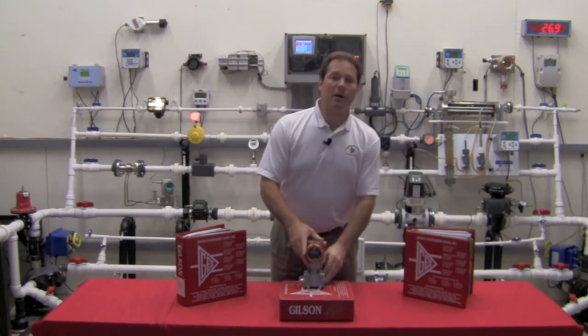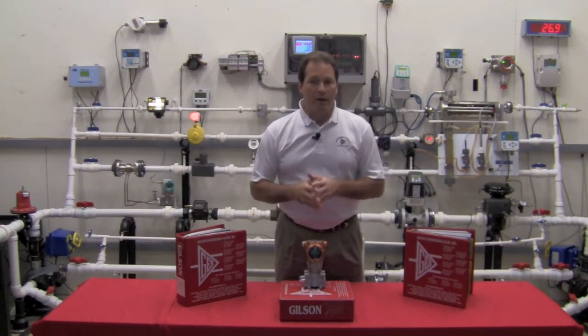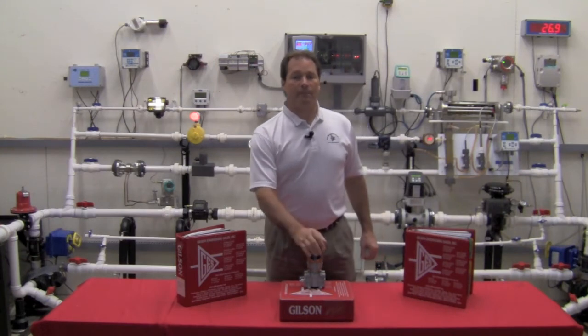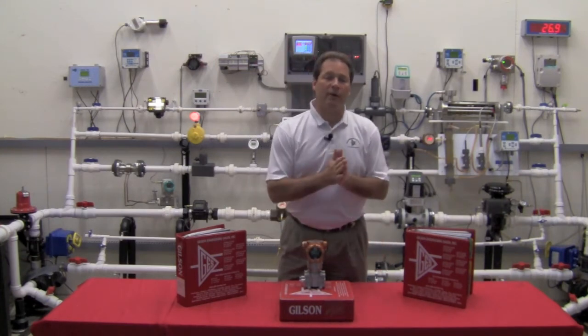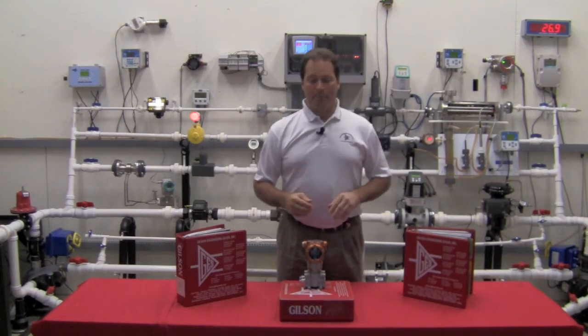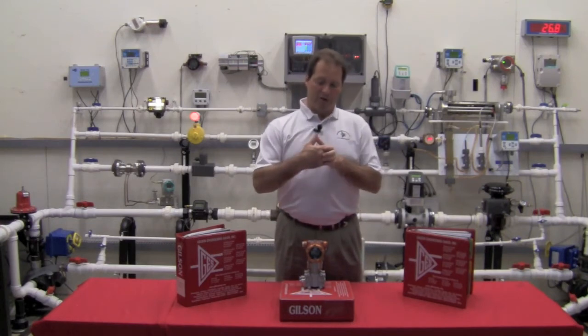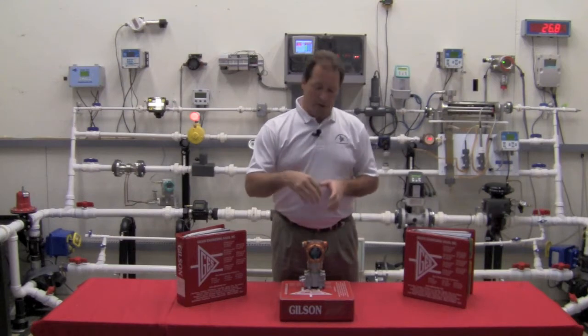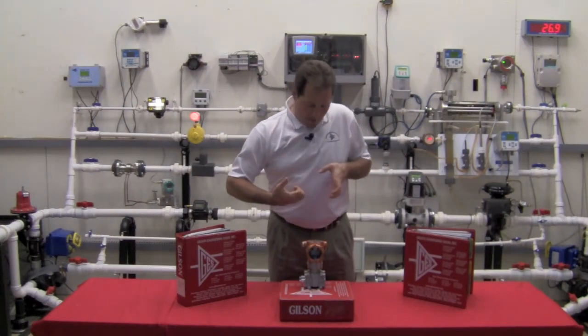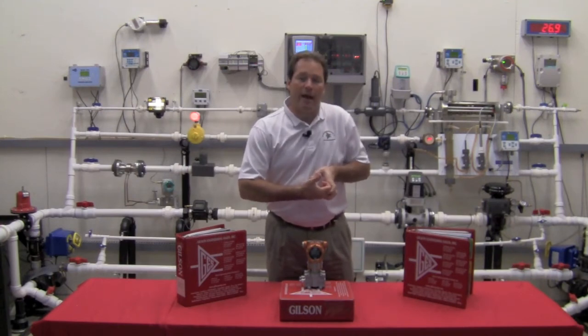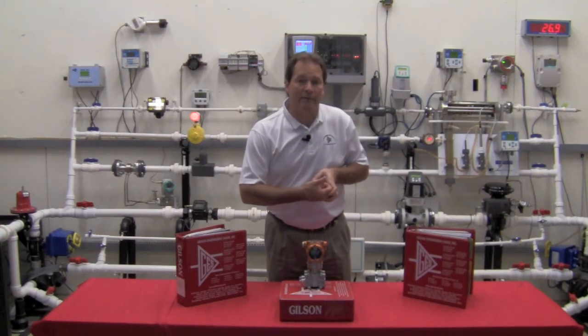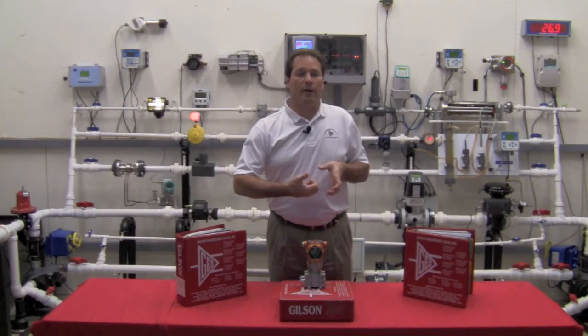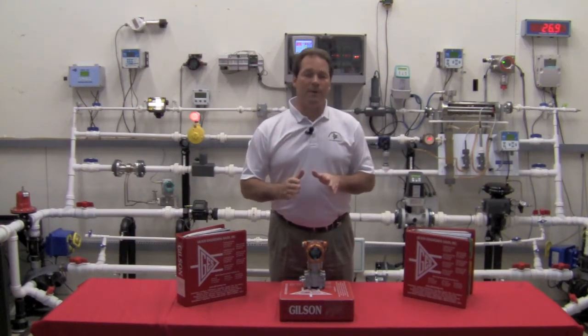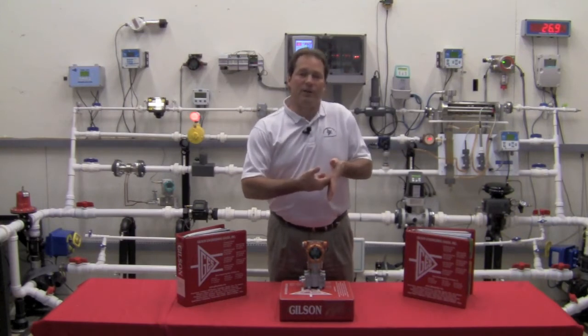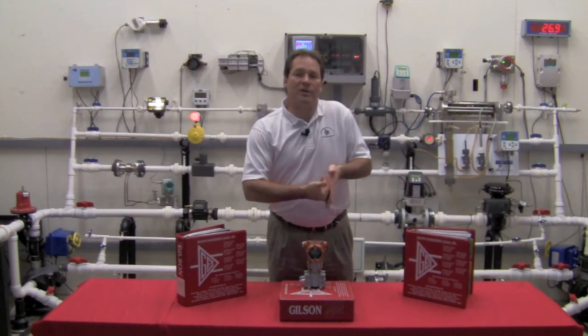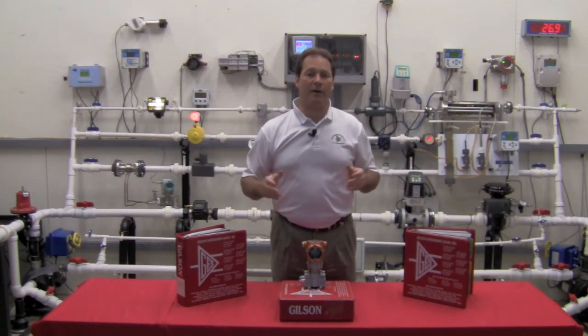And the way we set up our diaphragm is that, like all our competitors, we have ridges in our sensing diaphragm. Internally, we have a seal that the diaphragm backs up against when you overpressure the transmitter. What happens with the Yamatake transmitter is we match the ridges in the sensing diaphragm to the ridges in the internal seal. That way we have ridges lining up with ridges internally as we overpressure this device. When the overpressure goes away, the unit just reseats itself and goes back to its same shape. What most people do is have the ridged diaphragm up against a flat internal seal. When that ridge hits the flat, it squashes the ridges, it changes your zero, you need to recal, and your accuracy is going to be shot.